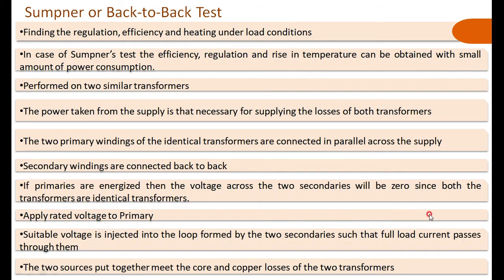Now we will go to the Sumpner's test, also called the back-to-back test. The Sumpner's test basically determines the parameters of the transformer and also helps us calculate the efficiency. The key difference from the OC test is that in the Sumpner's test the setup is kept running for a longer time, so that a rise in temperature can be observed — and the effect of that temperature rise on regulation and efficiency can be studied. That is the main advantage of the Sumpner's test.